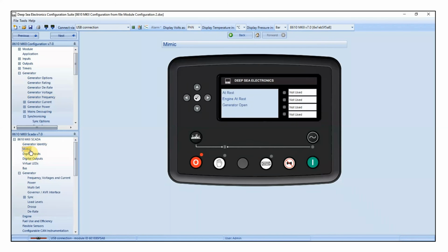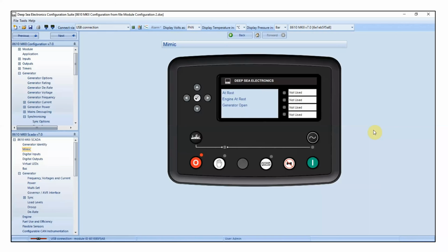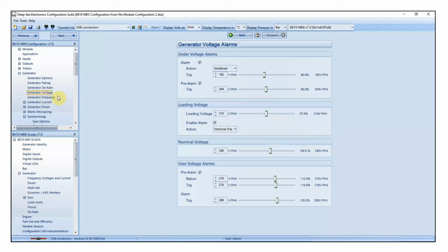So what we're going to look at now is how we set up the switch 2 for the AVR. The setup procedure for the switch 2 of the AVR is effectively exactly the same as the governor. The only difference this time is that rather than talking frequency, we're talking voltage. So we go to the nominal voltage, and we're going to increase the nominal voltage by 10%. In my example, that'll be 264. And we're going to write that to the controller.